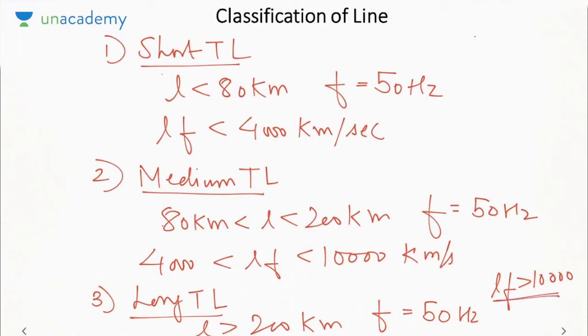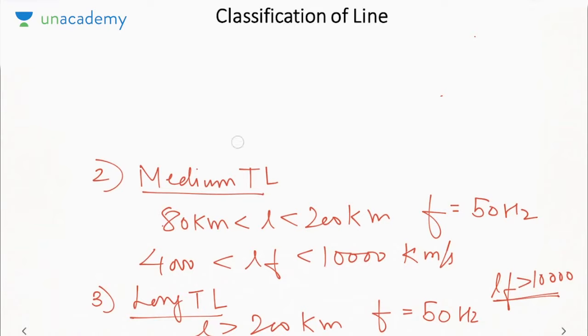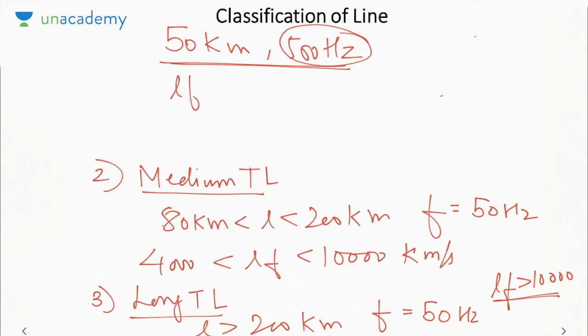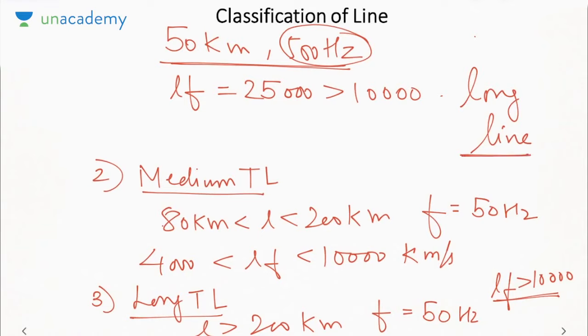Remember this criteria on LF, because sometimes the frequency may be changed when a question comes, so you have to change the criteria. For example, if I ask you, a 50 km long line operating at 500 Hz will be classified as what? From the length criteria it seems that it is a short transmission line, but I have changed the frequency. So L into F will be 25,000, which is greater than 10,000. So it is a long line. So classification is not only based on the length of the line but rather on the length into frequency.